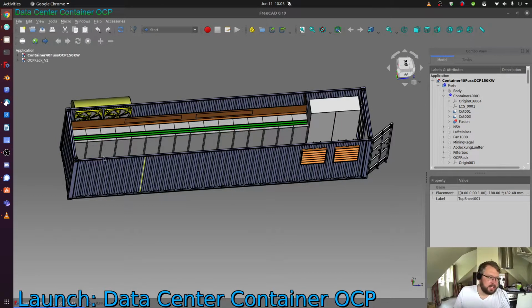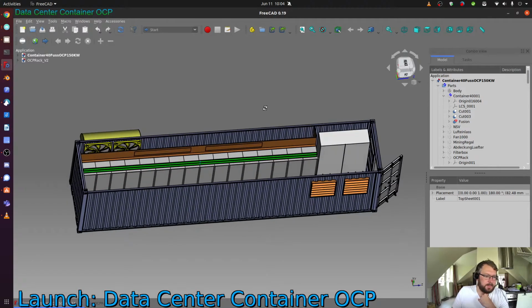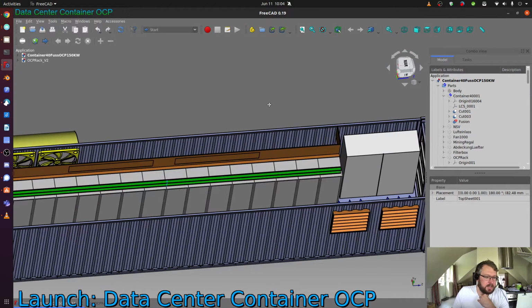This is why I designed this: OCP gear by standard is designed to go up to 35 degrees, which is the whole reason we can have a direct free cooling use case for data centers and don't require any actual cooling at all — we only move fresh air through the data center. This is obviously only applicable in regions where the temperature doesn't go above 35 degrees year round, which limits the use case, but makes this data center very simple and easy.